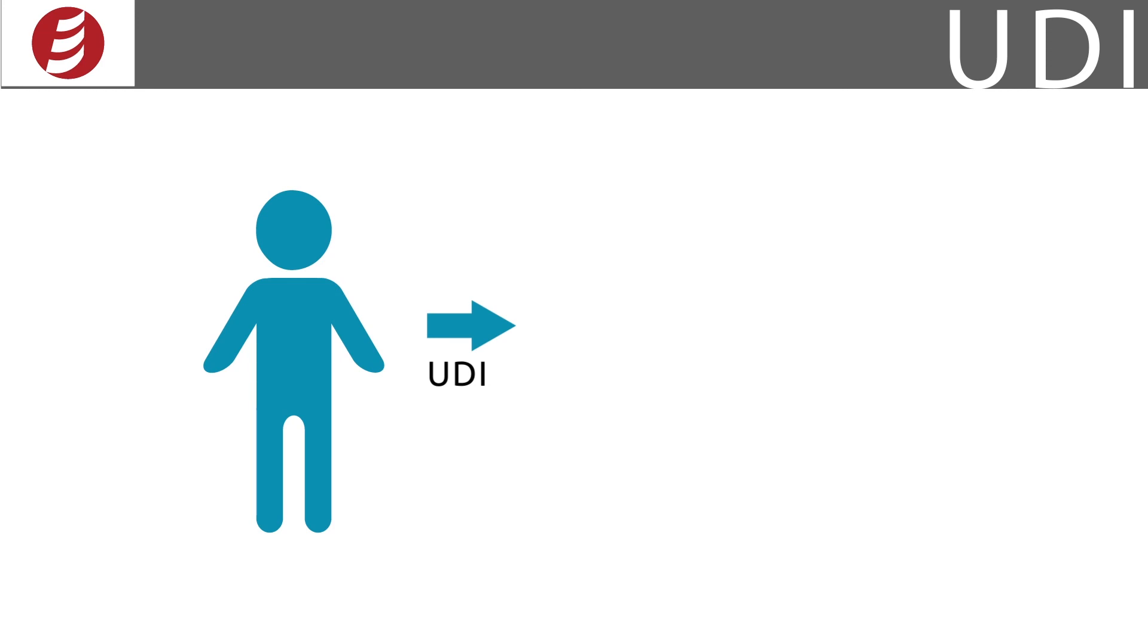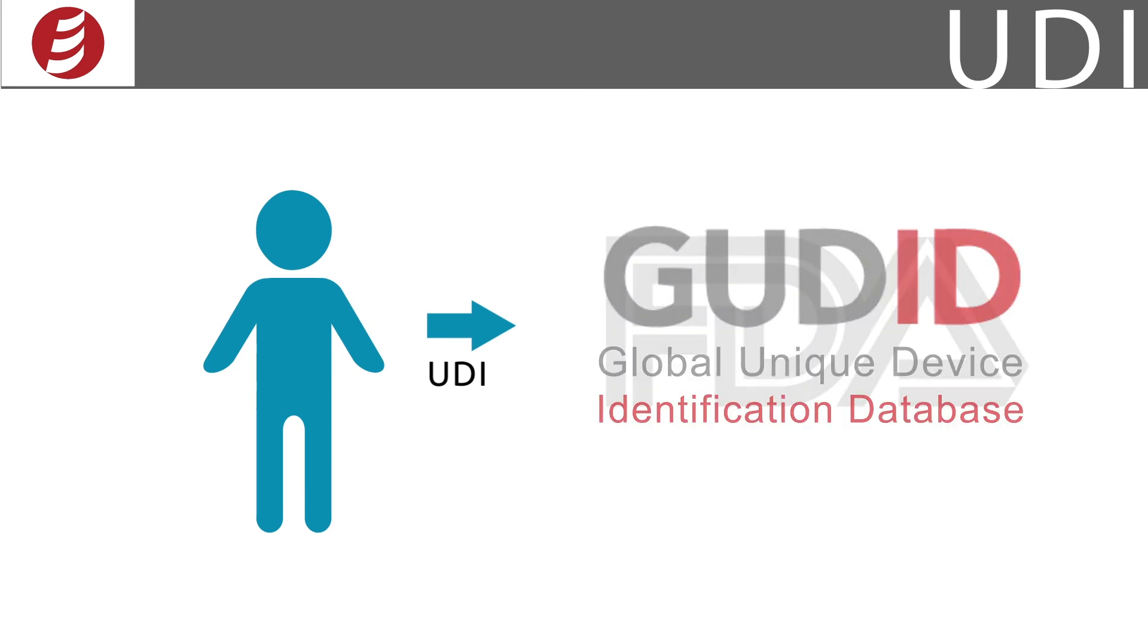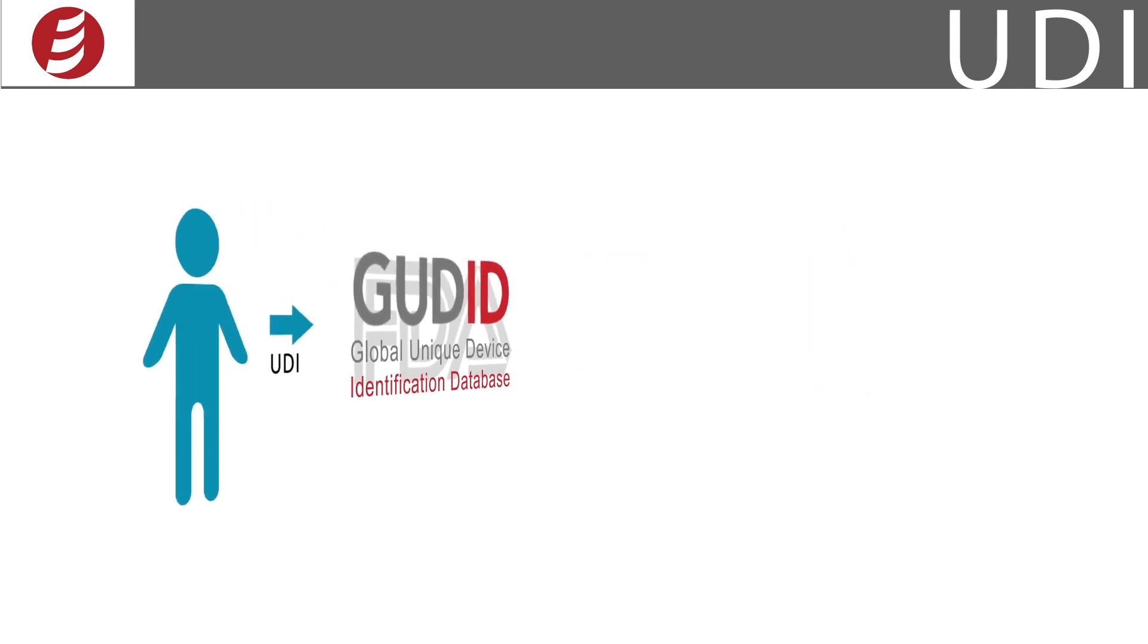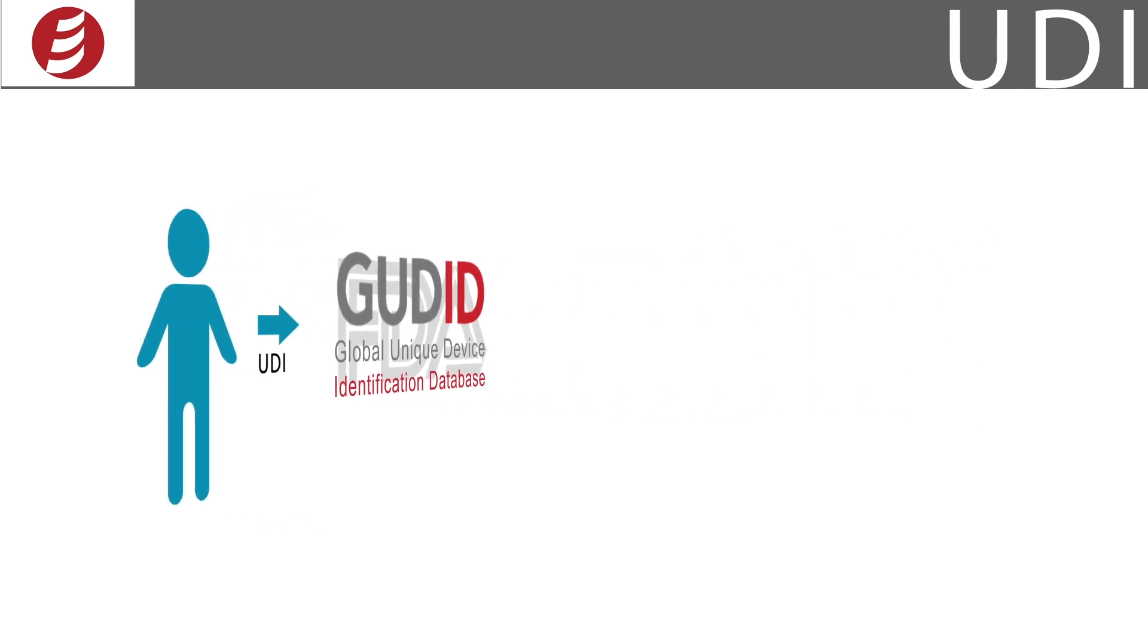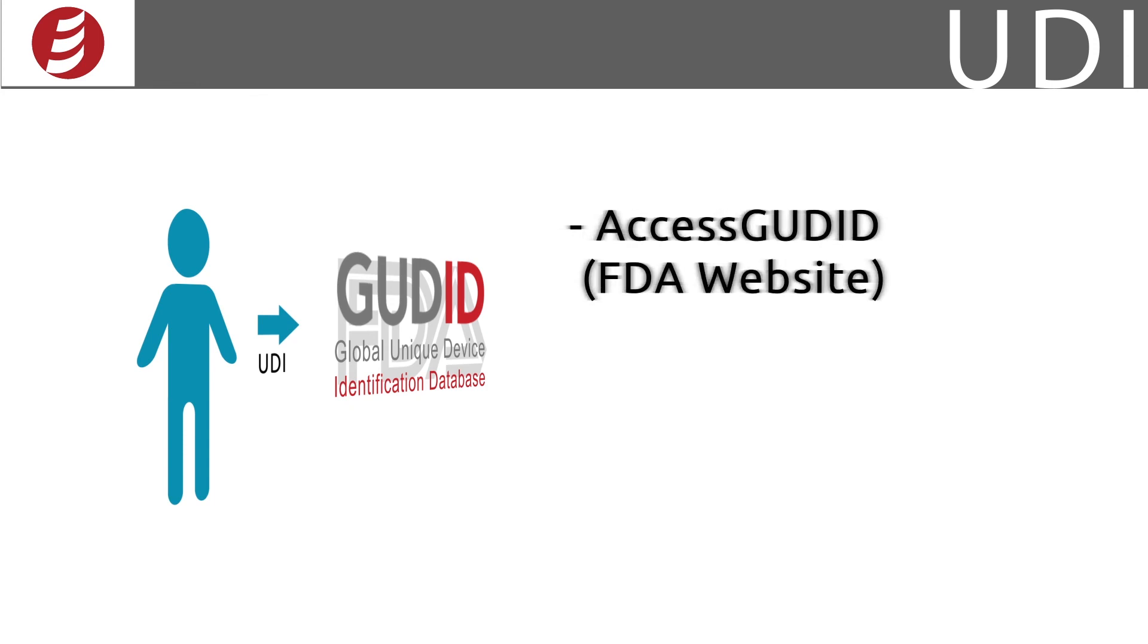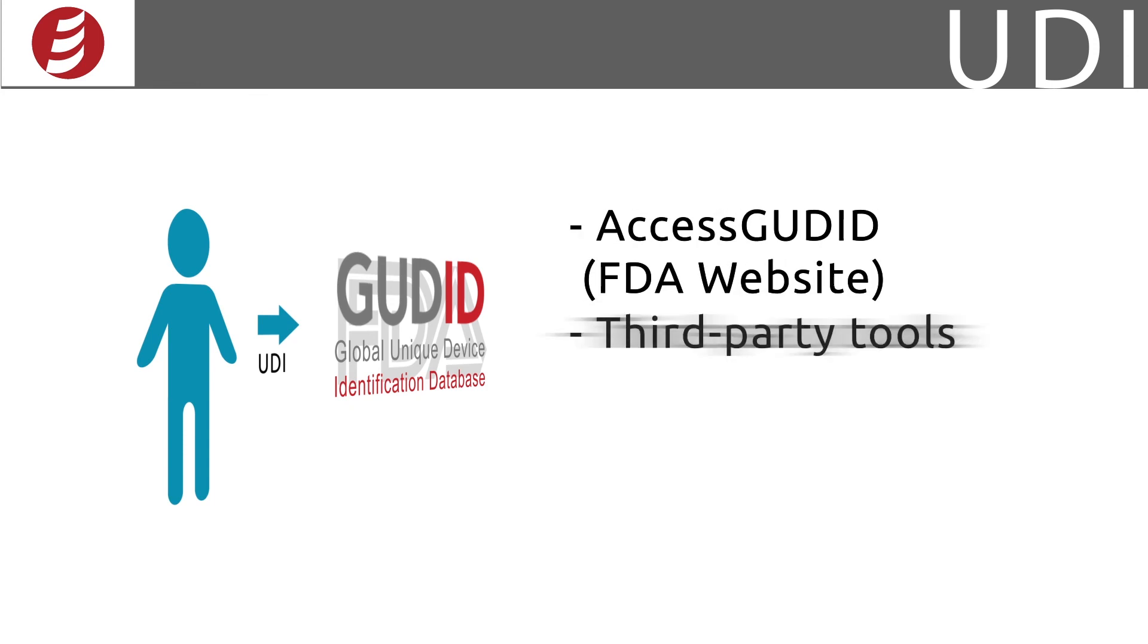You then take the UDI and transmit it to FDA's GUDID, the Global Unique Device Identification Database. You have a few choices for data submission avenues. Most smaller organizations will utilize FDA's AccessGUDID web portal. There are some third-party tools available to help as well.